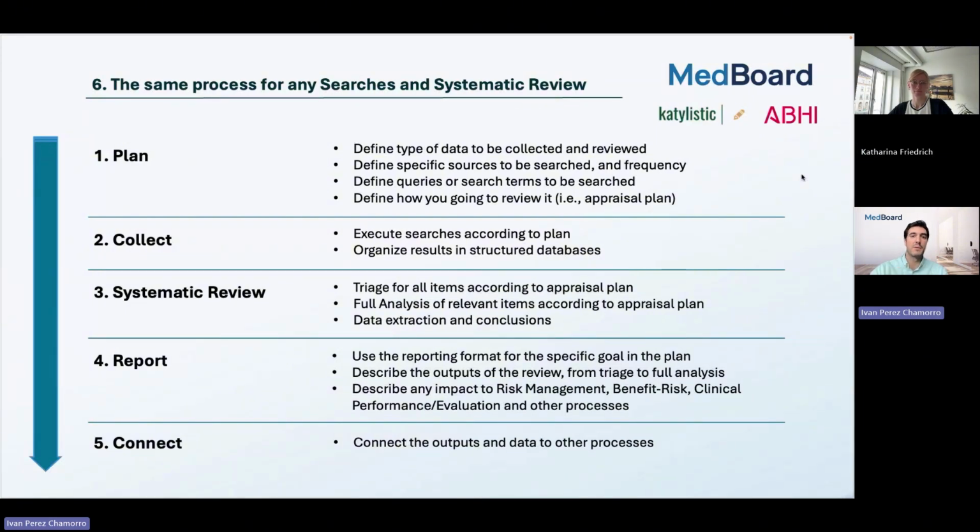This is one of the areas where I see more gaps. People have it for literature, and I think that, through the feedback from notified bodies and so on, it has improved massively. But for example in terms of PMS and other activities, maybe that's not that well established. So you have an update, whether it's relevant or not relevant, whether the risk identified there you have or not have. So all of this has to be in a form. It has to be in a structured process.